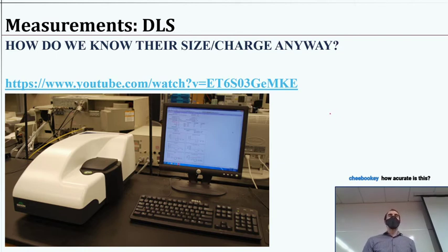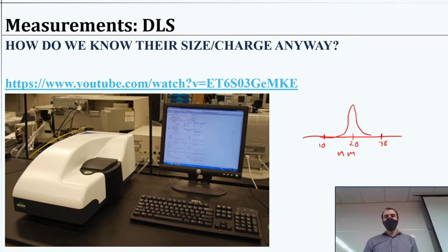You might be wondering how accurate these are, and really it's pretty accurate. I would say it depends a little bit on how precisely dispersed or how precisely sized your particles are. So if you manufacture nanoparticles that are all pretty much exactly 20 nanometers in diameter, have uniform shape, uniform everything, then it's going to give you a very sharp peak.